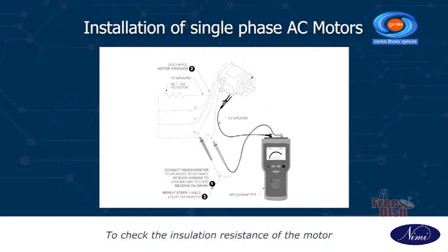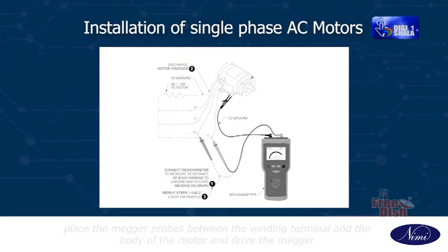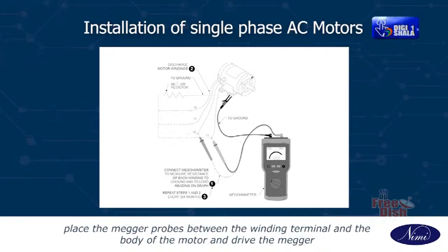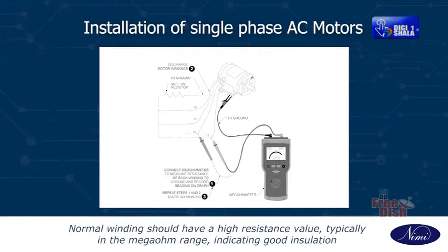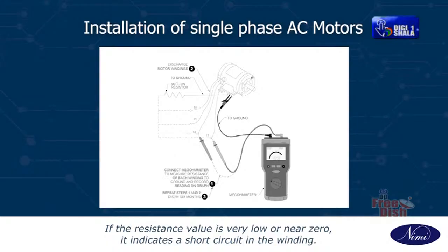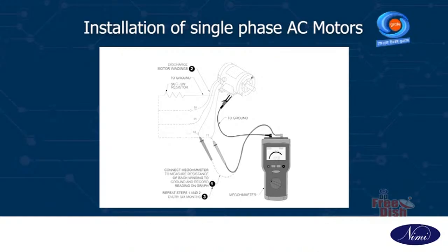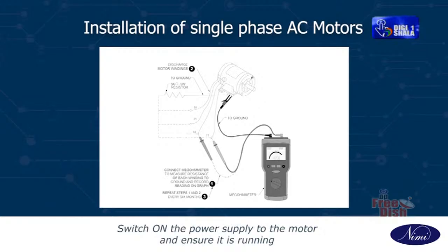To check the insulation resistance of the motor, place the megger probes between the winding terminals and the body of the motor and drive the megger. Normal windings should have a high resistance value, typically in the megaohm range, indicating good insulation. If the resistance value is very low or near zero, it indicates a short circuit in the winding. Step 11. Switch on the power supply to the motor and ensure it is running.